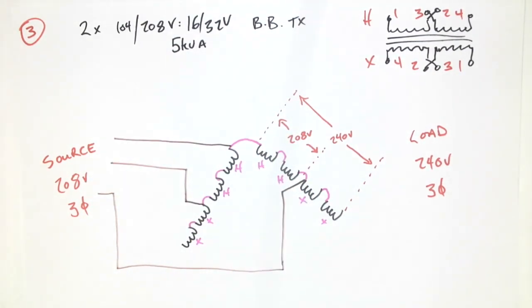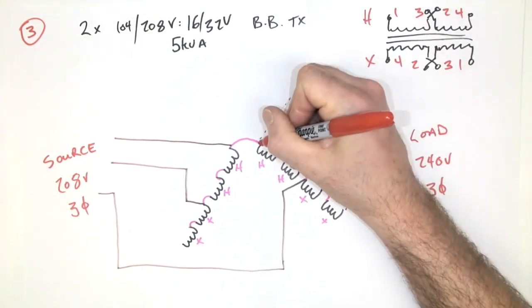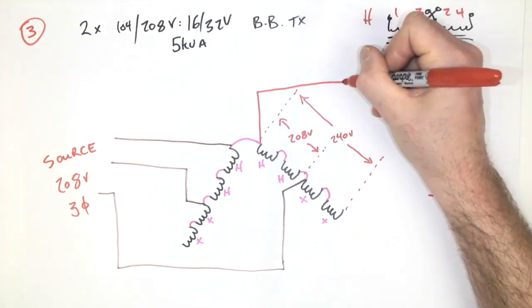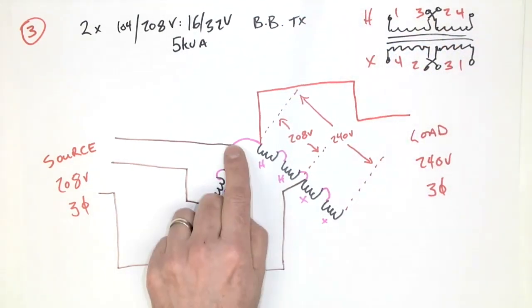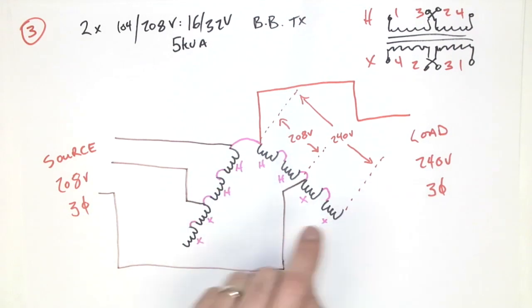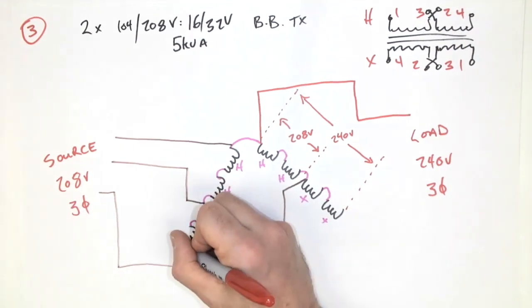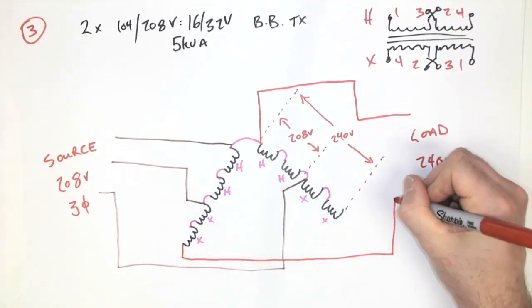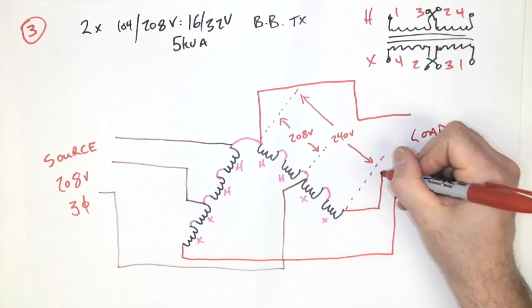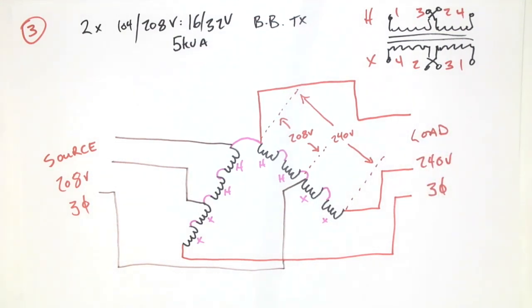All right, now the load is going to be supplied, a 240 volt three-phase load, and that 240 volt load we are going to have off of this point here. So I've got a connection that's going to come off the common point, right? This connection here connects to both the load and the source. I'm going to have a connection here from my X terminal, and finally from this one here. So now we've got our connection for both the source and the load. And now we can go ahead and calculate the total kVA of this particular bank.